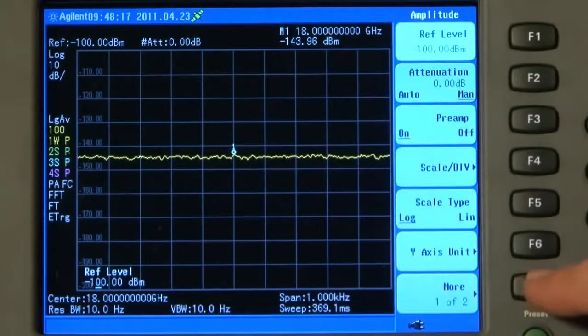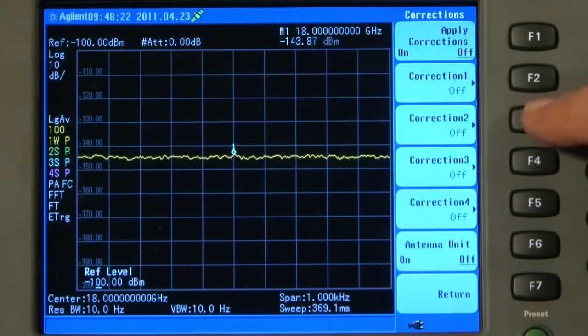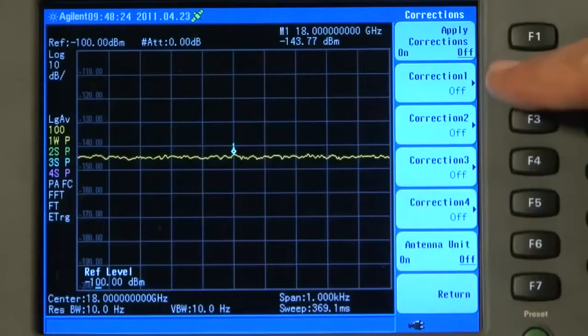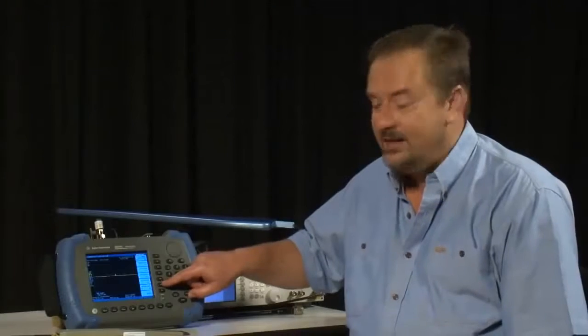I simply press Return, press More, press Correction. And here you can see a range of correction factor tables can be stored, which we can turn on, and then turn on the antenna units to display in true field strength.